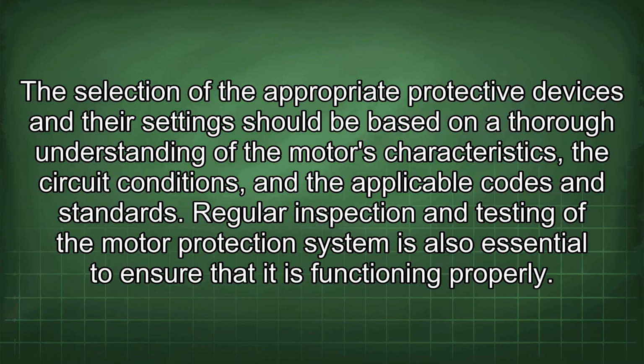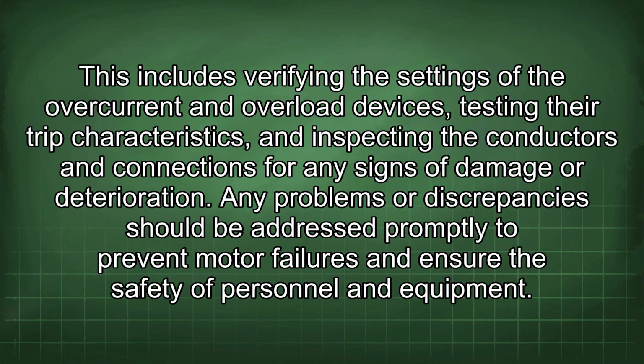The selection of the appropriate protective devices and their settings should be based on a thorough understanding of the motor's characteristics, the circuit conditions, and the applicable codes and standards. Regular inspection and testing of the motor protection system is also essential to ensure that it is functioning properly. This includes verifying the settings of the overcurrent and overload devices, testing their trip characteristics, and inspecting the conductors and connections for any signs of damage or deterioration.